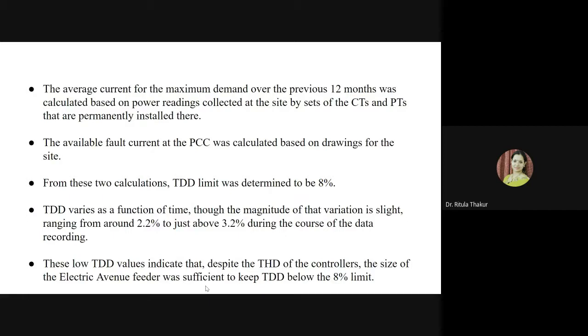They were provided the drawings, so accordingly the available fault current at the point of common coupling was calculated. And from these two calculations, the TDD limit was determined to be 8%, which is not that high. It is also observed that the TDD varies as a function of time, though the magnitude of that variation is slight. It can range from about 2.2% to just about 3.2% during the course of the data recording.